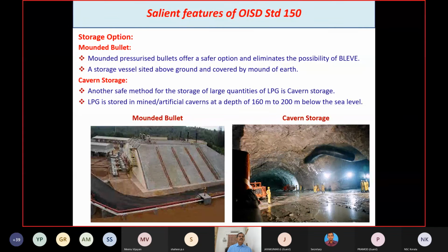Another one is the mounded bullet. The mounded pressurized bullets offer a safe option and eliminate the possibility of BLEVE, that is boiling liquid expanding vapor cloud explosion. A storage vessel sited above ground and covered by a mound of earth, so it is fully covered by the earth. Then cavern storage is another safe method for storage of very large quantities of LPG. Suppose you want to store 1 lakh tons or more, you can go for cavern storage. The LPG is stored in mined artificial caverns at a depth of 160 meter to 200 meter below sea level. So they are drilling the rocks below sea level, about 160 meter to 200 meter, and making a tunnel where they are storing the LPG.